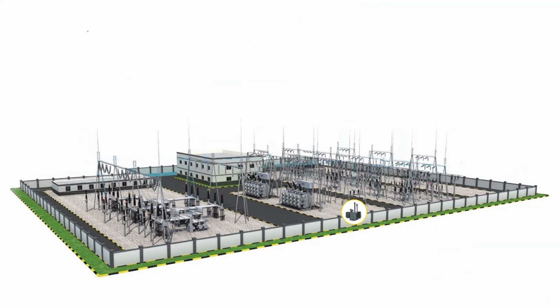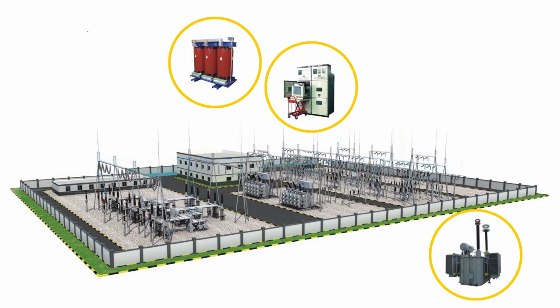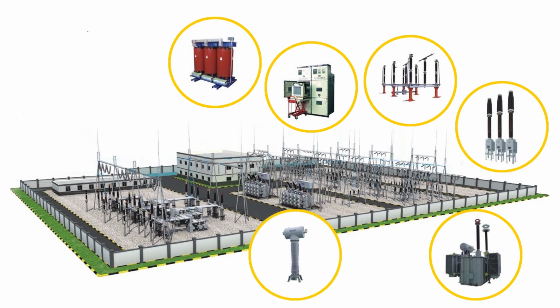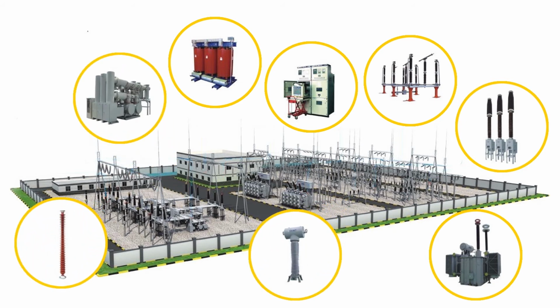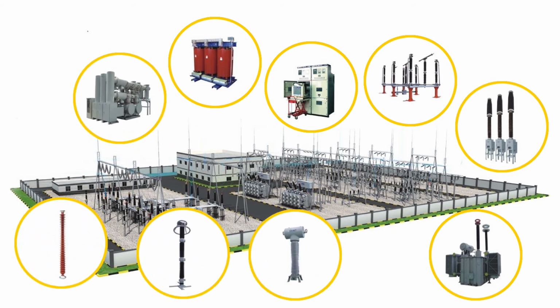So where do we find partial discharge? Well, you'll find partial discharge activity in all types of high voltage power assets, from switchgear to transformers to overhead lines and underground cables. Partial discharge causes degradation and failures. Experience shows that partial discharge activity is a contributory factor in over 80% of disruptive substation failures. It's the most reliable indicator of the true condition of insulation in live assets.